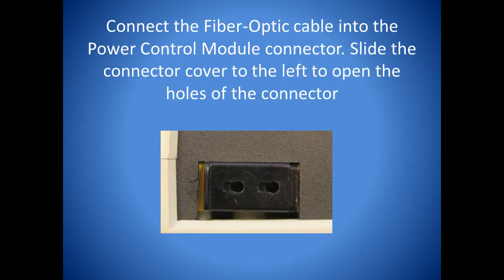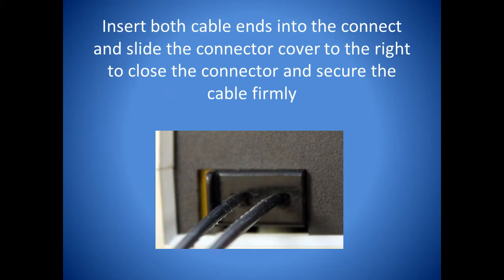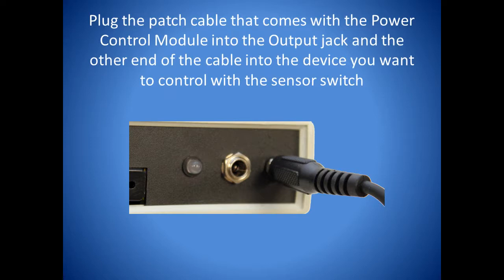Connect the fiber optic cable into the power control module connector. Slide the connector cover to the left to open the holes of the connector. Insert both ends of the cable into the connector and slide the connector cover to the right to close the connector and to secure the cable firmly. Plug the patch cable that comes with the power control module into the output jack labeled switch output and the other end of the cable into the device that you want to control with the sensor switch.